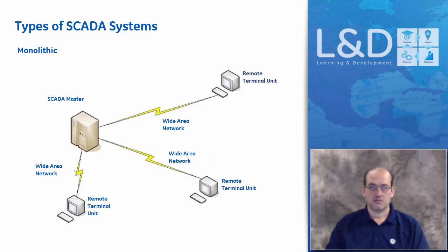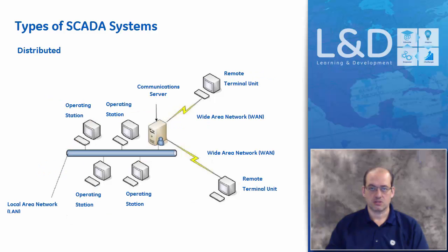Over the years, SCADA has evolved from a monolithic architecture, where you had only one framework where all the applications would report, to a networked architecture. Today's SCADA systems are able to take advantage of the evolution from mainframe-based to client-server architecture. These systems use common communications protocols like Ethernet and TCP/IP to transmit data from the field to the master control unit at a very high speed.